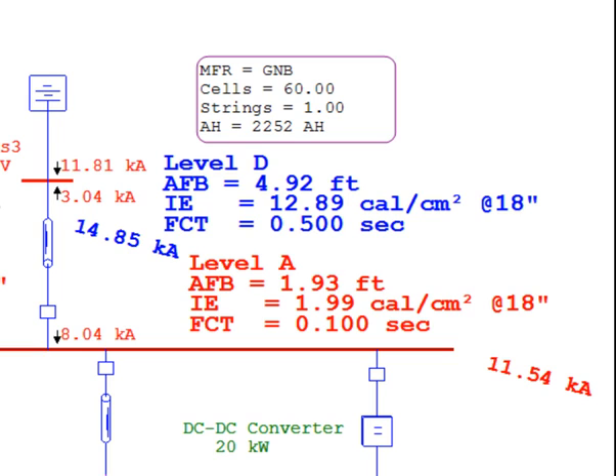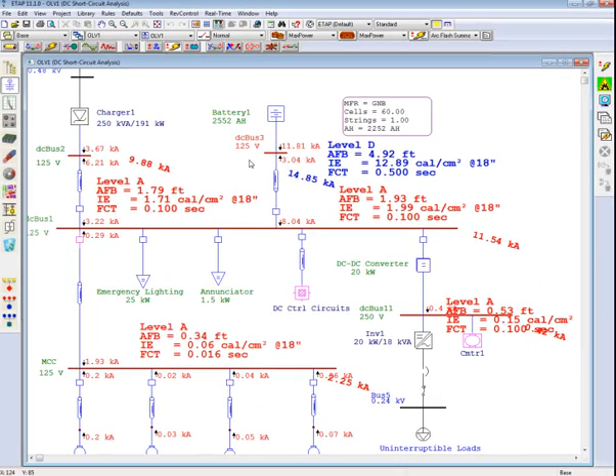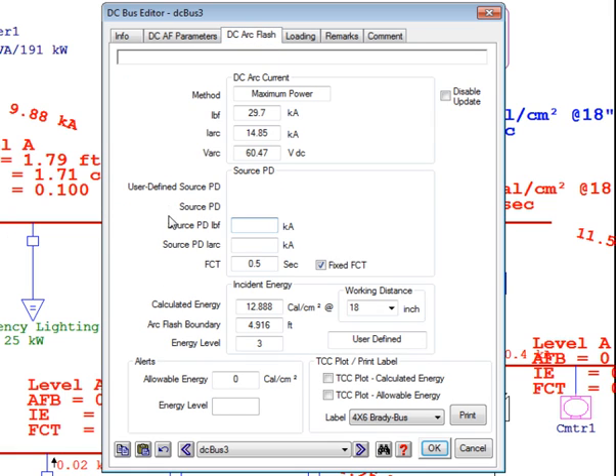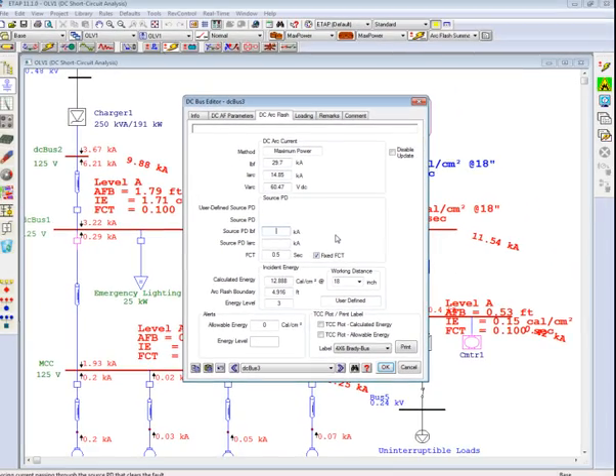As previously discussed, the fault clearing time can be predefined by the user to calculate the amount of energy released by the arc. It is advisable that when using the maximum power method, the user uses a longer clearing time or the approximated time of exposure that a worker would be exposed to in the event of an arc flash — for example, a 1 or 2 second fault clearing time. In this instance, we have predefined the fault clearing time to be half a second, and based on an arcing current of 14.85 kilo amps, we get an incident energy of 12.89 calories per centimeter square. Additionally, if you double click on a bus at any location and switch to the DC arc flash page, you will see the energy results, the flash protection boundary, and the energy level which indicates approximately how much energy there is in the system.